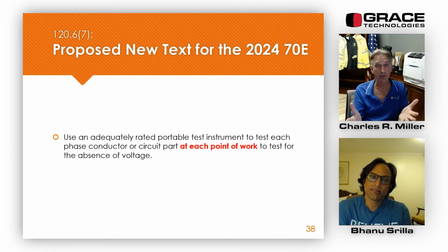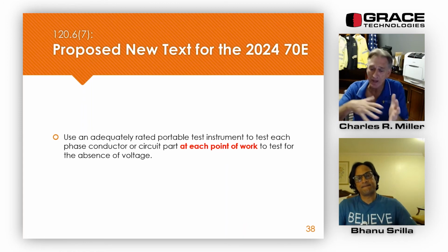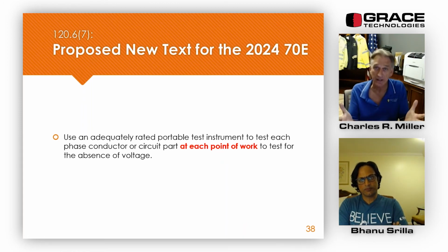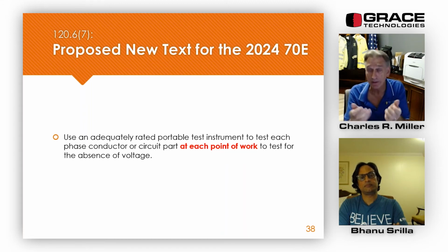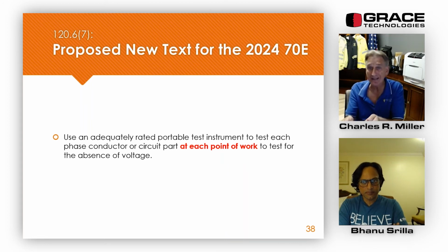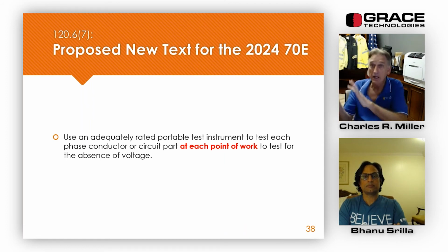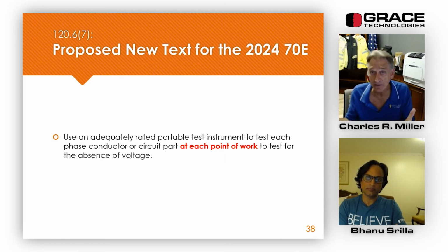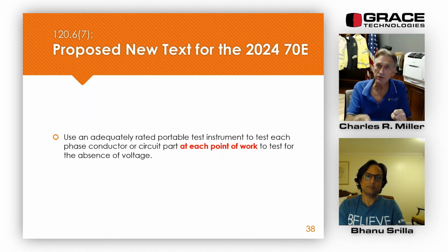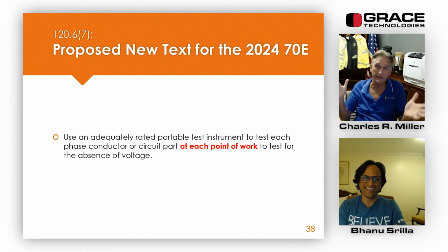All right, let me give you another example that gets even a lot worse. You've got a building where all the equipment is being taken out of it. It was an industrial plant. The service coming in on the outside has been disconnected. Normally, you would check the line side, and put that line side and the disconnect there. Everything would be electrically safe inside the building. With this new wording, someone is going to have to be dressed up, suited up, and test every disconnect, every conductor, everything in that building, even though it's been disconnected on the outside.